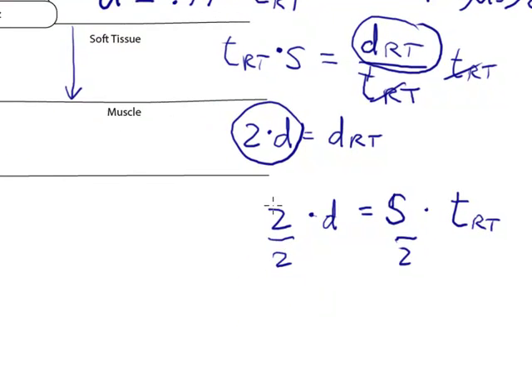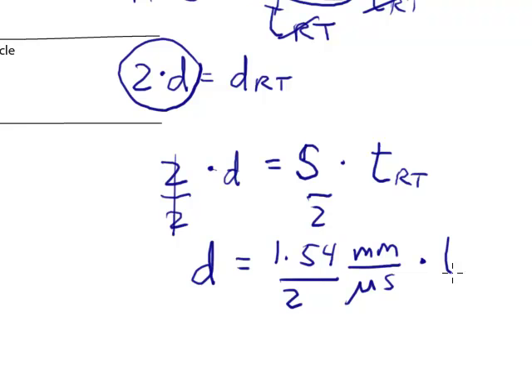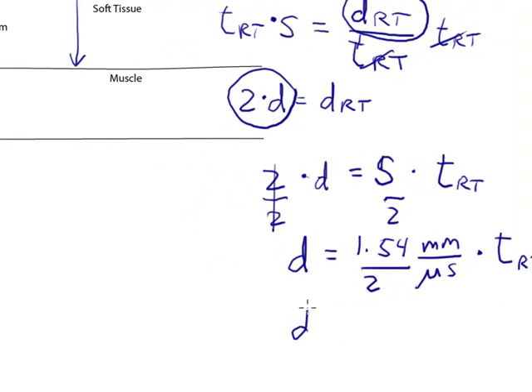which cancels there. So my distance to the reflector is equal to the speed in soft tissue, which is 1.54 mm per microsecond, divided by 2 times the round-trip time. So this comes out to be the distance is equal to 0.77 times time.